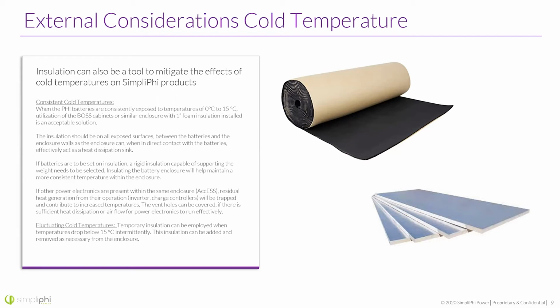Temporary insulation can be employed when temperatures drop below 15 degrees Celsius intermittently. The insulation can be added and removed as necessary from the enclosure. I mean, obviously you can easily pull and put in some sort of insulation if it's something like this, or even like the rigid foam. Oftentimes we can kind of adjust that based on the time of the year.